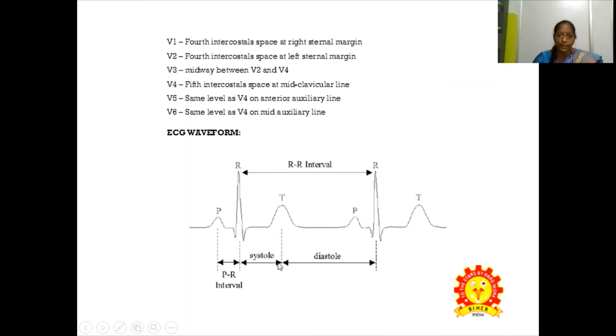This shows the ECG waveform and the intervals of more importance to us, such as the PR interval and the RR interval, and the systolic and diastolic time periods. This ECG recording method uses electrode systems. Metal plate electrodes made of silver chloride are placed at the desired limb positions. Good contact between electrode and skin is ensured with the help of gel and belts.